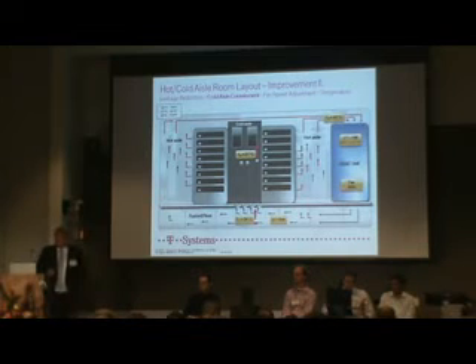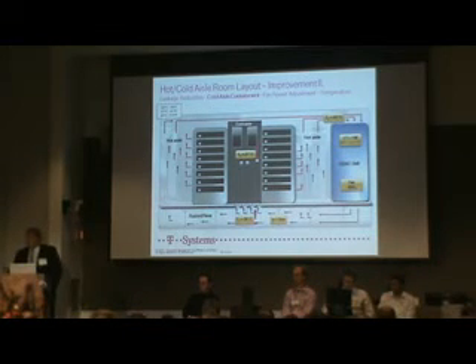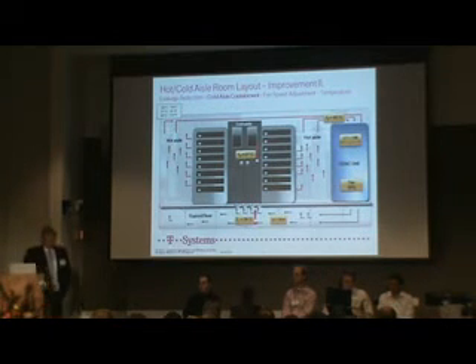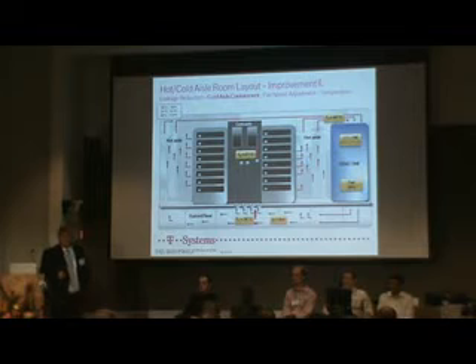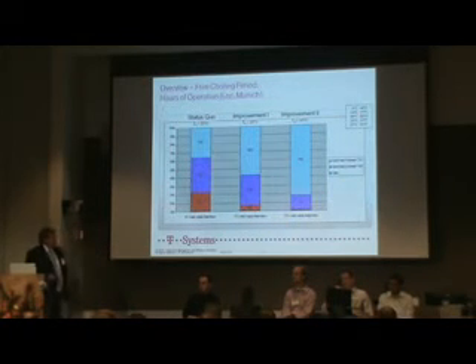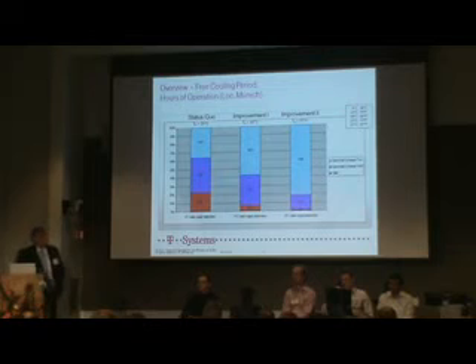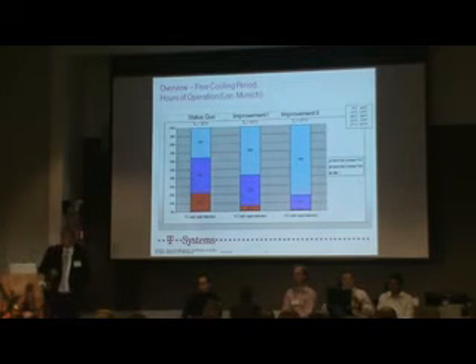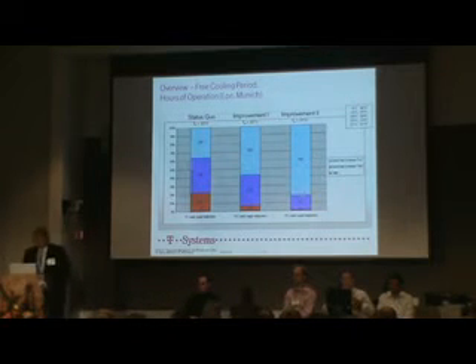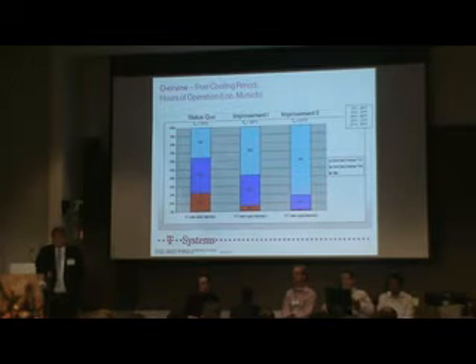And if we increase the server inlet temperature to the latest ASHRAE recommendation, let's say 27 degrees server inlet temperature, you have a need for 26 degrees centigrade in the raised floor. And this means, for a location like Munich, we can operate the data centers with less than 90 hours per year with the chillers. And this is a lot of energy savings in the cooling part of the data center.